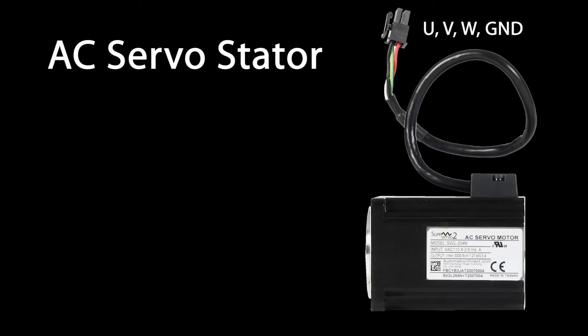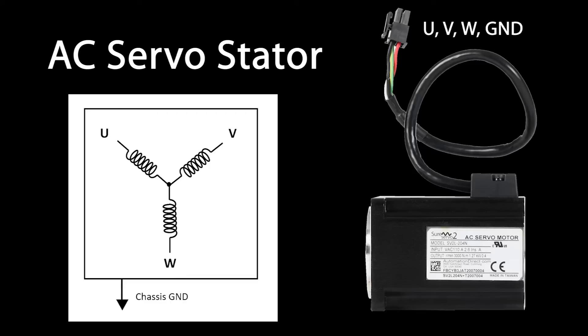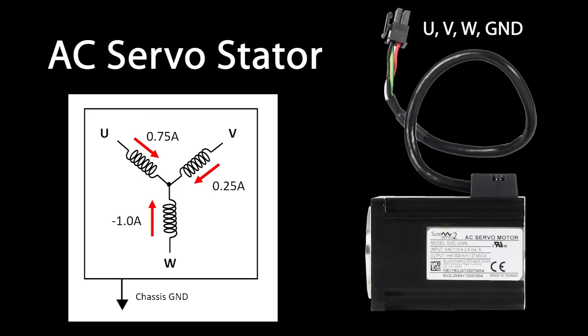This is the stator that was around the rotor we were just playing with. It has the three UVW wires plus chassis ground coming out. It's wired like this. The drive's whole purpose in life is to adjust the currents in these three windings to create just the right magnetic field in the stator. And of course this has to be a zero sum game. That is, if the drive forces 3 quarters of an amp in here and another quarter amp in here, it better take one amp out here. The three of these always have to sum to zero.